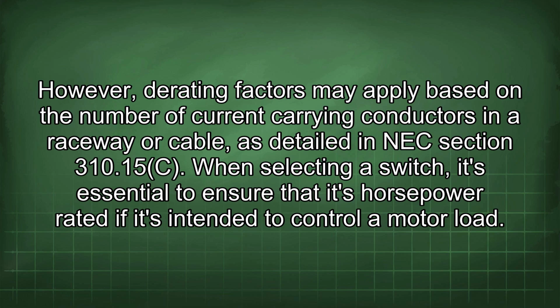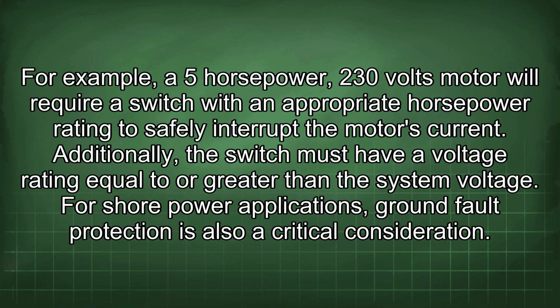in NEC Section 310.15(C). When selecting a switch, it's essential to ensure that it's horsepower rated if it's intended to control motor load. For example, a 5 horsepower, 230 volts motor will require a switch with an appropriate horsepower rating to safely interrupt the motor's current. Additionally, the switch must have a voltage rating equal to or greater than the system voltage. For shore power applications, ground fault protection is also a critical consideration.